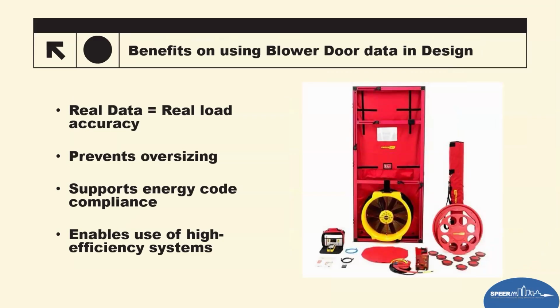So the benefits of using real blower door data, and we'll see more of this a little bit later, is basically real data equals real load accuracy. Everything that they turn in to you for a permit request is, and I'll just use it this way, a hypothetical or an assumption. It's a preliminary or projected model to say this is what we feel we're going to do, these are the test results we feel we're going to accomplish. And of course, sizing is now based on those assumptions. If the HVAC guy is not using the correct assumptions, we'll see what that looks like a little bit later, that changes everything about sizing in the building when it comes to HVAC.